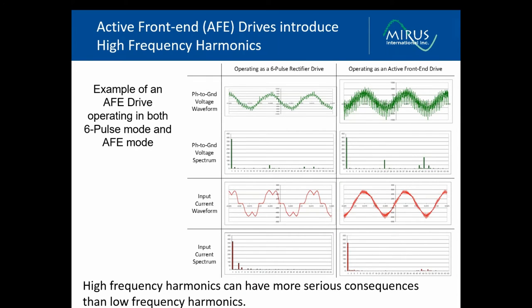So let's take a few minutes and we'll discuss a little bit about the high-frequency noise and that effect that the AFE drives introduce. So these graphs shown here are an application on a marine vessel where the drives that were being used were configured such that they could be operated as a standard six-pulse drive, but also operated as an active front-end drive. And this allowed the authors of the paper, where this information came from, to run in the two modes and take measurements.